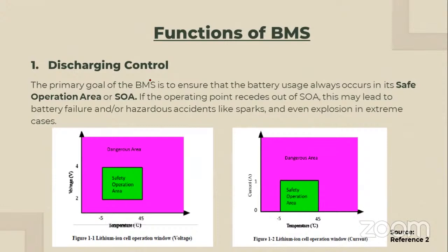The BMS may give commands or send signals to the connected load to get it derated. For these batteries, maintaining voltage is critical. For a chemistry like lithium-ion, each cell has an operating window with respect to temperature and voltage. If the cell voltage rises beyond about 3.5 to 3.6 volts, it is not safe, since there's a chance of overcharging, which results in higher temperatures. If this heat isn't evacuated properly, damage can occur to the battery pack.